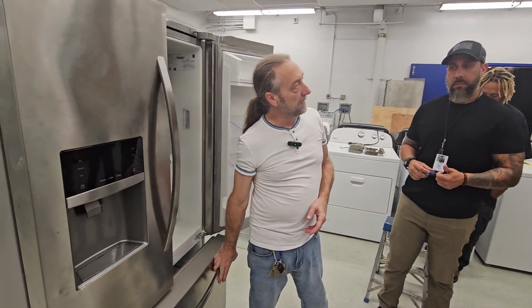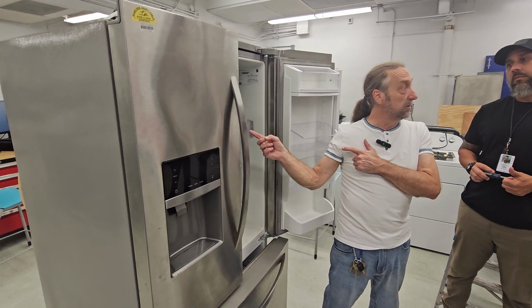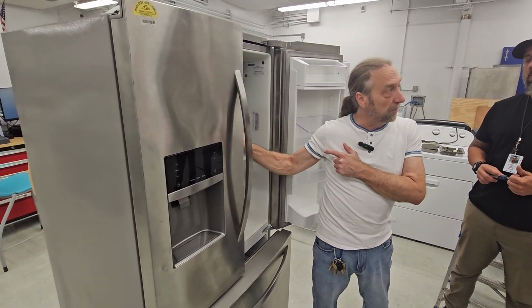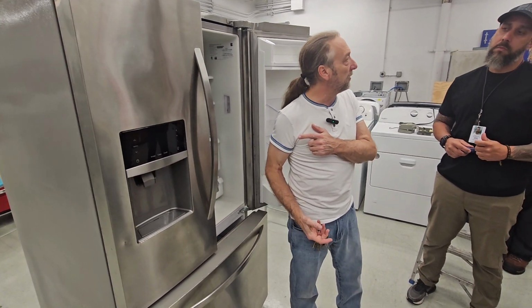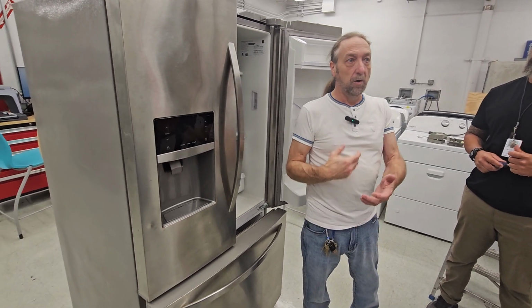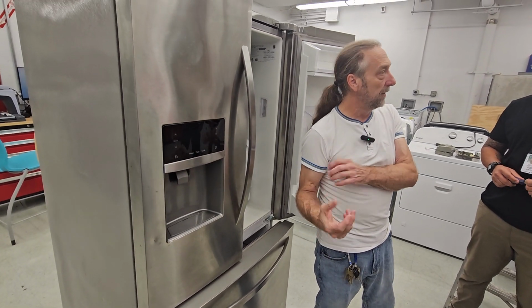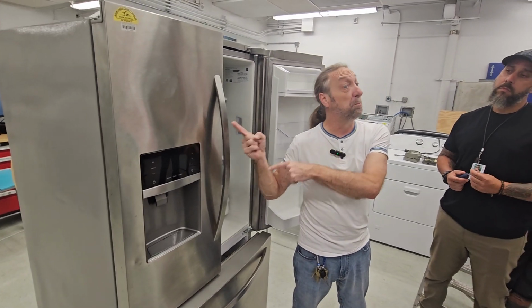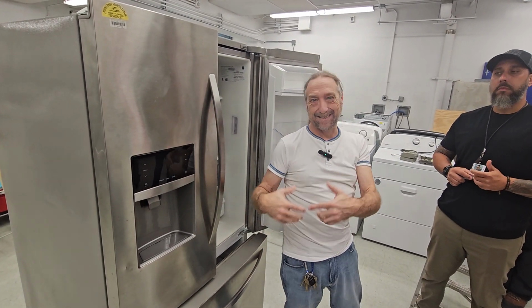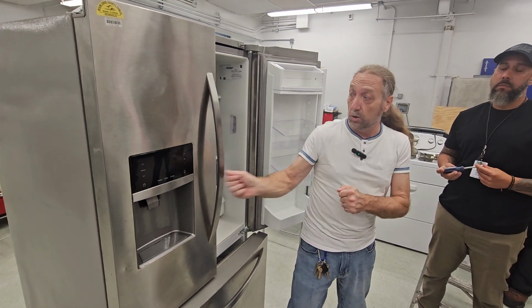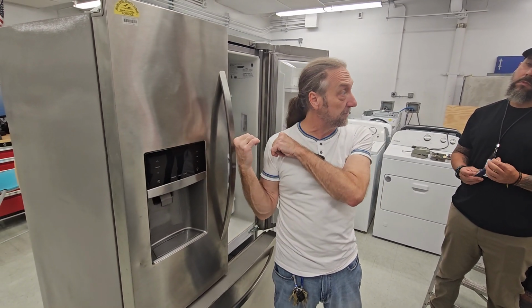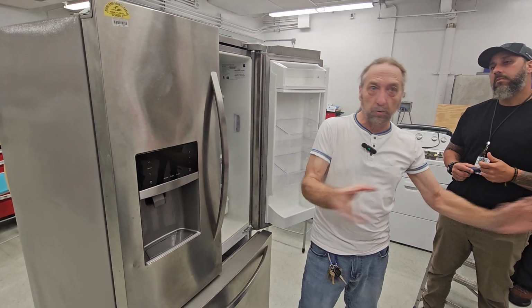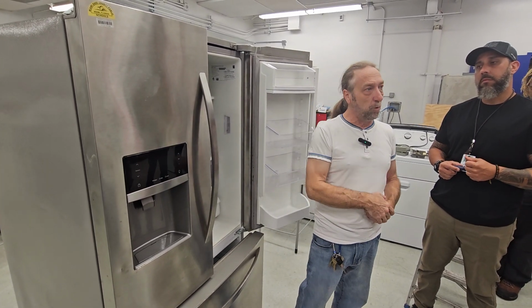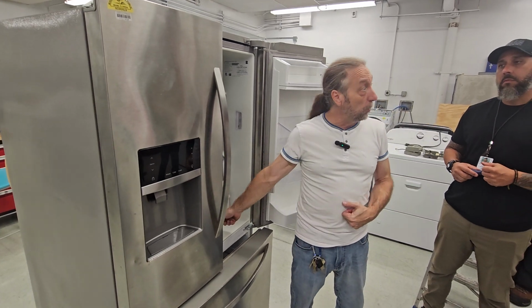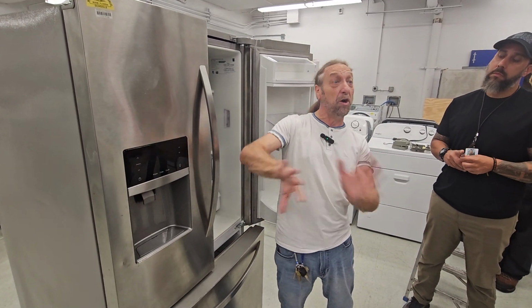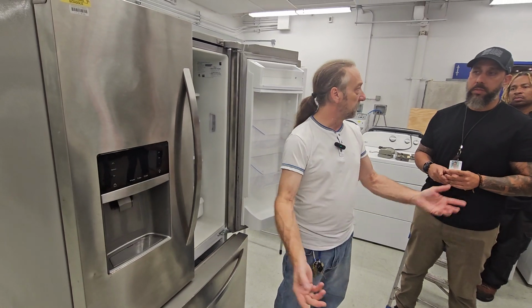What if the sensor is good, but the wires that run from the sensor to the board, one of the wires got chewed up by a rat or got too hot and melted somewhere? So the sensor may be good, it's just the board can't read it, or the board says it's open or shorted. So just because diagnostics tells you that it failed the test, that doesn't mean stop what you're doing, order the part, and come back. Because you'll order the part, come back, open the whole machine up, take all the shelves out, put in a new sensor, put it all back together and plug it in, and you got the same problem.